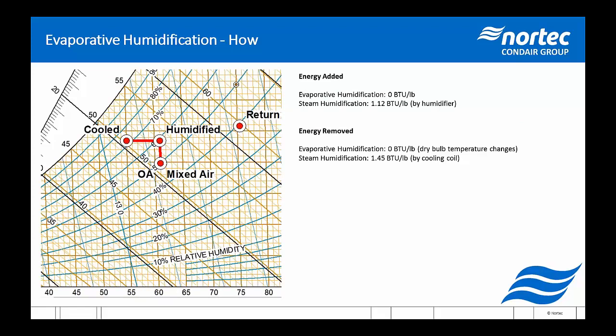So here's an example of when an evaporative humidification system can be extremely effective. This is a day when it's about 62 degrees outside, 61 degrees outside, and 50% humidity, probably around this time of year, actually. So your economizer's running, but in order to maintain your 40%, you need to humidify that air. But you also need to cool that air in order to maintain your 72 degrees in space.